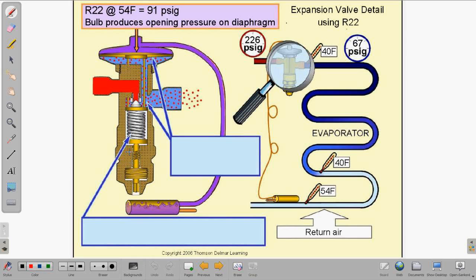Now, here's what usually goes wrong with the TXV valve, and that is this connection of the tubing up here at the top of the diaphragm is pretty fragile. And this tube here is about the size of a pencil lead. It's very small. And there's vibration, and it gets moved around during installation and so forth. And this junction right here tends to break over time and leak. So it leaks out all of the refrigerant from the sensing bulb. So there's no more downward pressure to open up the valve.